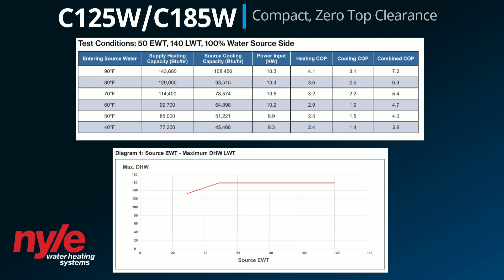If you were to do air source with us, that would also include things like defrost and fan power. So we are here to be transparent and give you all of the information that you need in order to design these into your projects and know what performance you're going to get from them. We also publish our LWT curves. As you can see, this particular unit is a very flat 160 degree leaving water temperature for most of its operating range. Once it gets to the bottom, it starts to derate a little bit down towards 140. But it does give you that maximum LWT for the majority of its operating condition.